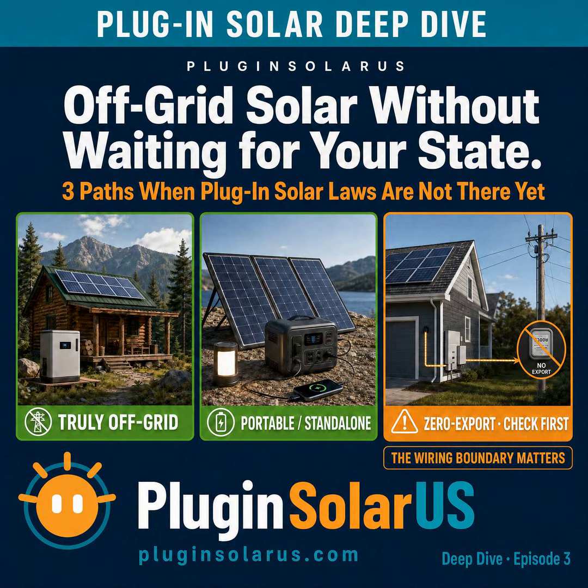Mike, give us the bottom line in 3 takeaways. First, you can use solar without waiting for state plug-in solar legislation when the system stays independent of utility wiring, such as a true off-grid setup or a portable standalone setup. Second, permanent off-grid PV and battery systems can still require local permits, inspections, property approvals, and code compliance. Third, zero export is not the same as off-grid. If a system operates in parallel with utility-supplied wiring, contact the utility and local authority before proceeding.